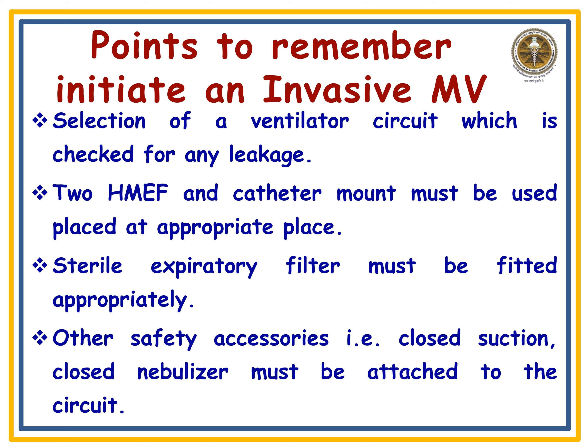There are important points to remember when initiating invasive mechanical ventilation. First, select the ventilator circuit and check for any leak prior to connection. Two HME filters (heat and moisture exchangers or bacterial filters) must be used in the circuit, and one catheter mount is used at the appropriate place. One sterile expiratory filter must be fitted in the assembling unit. Other safety accessories like a closed suction set and a closed nebulizer must be attached to the circuit.